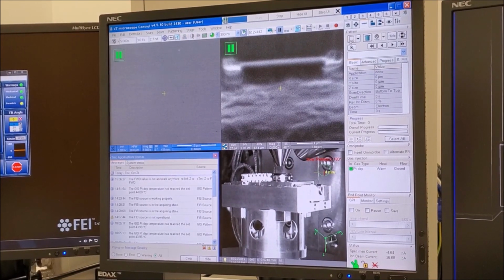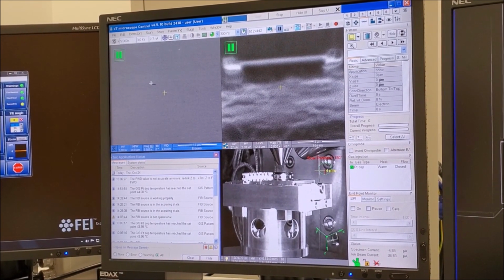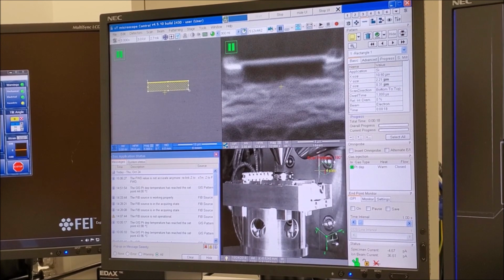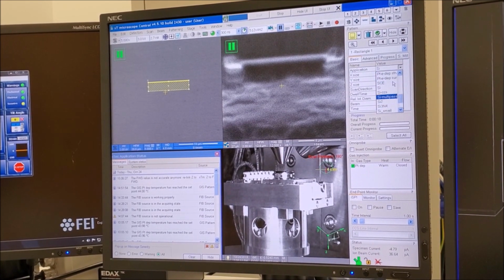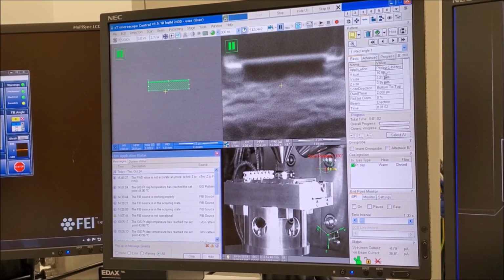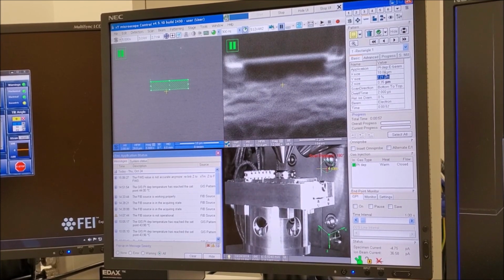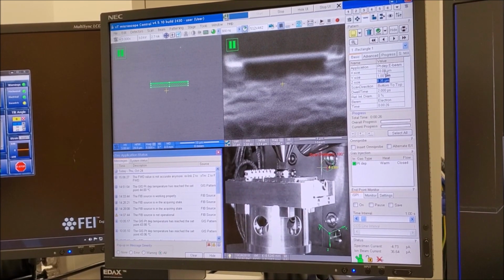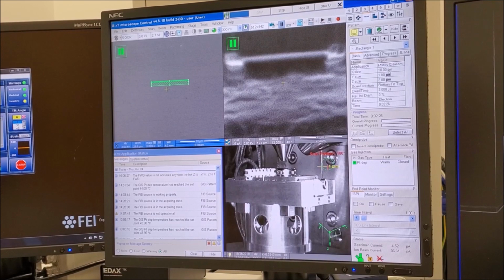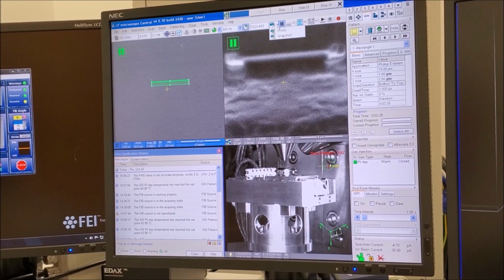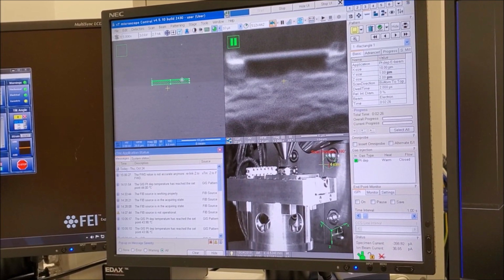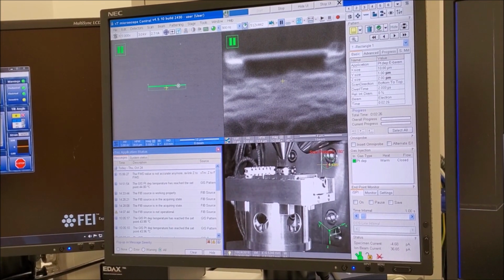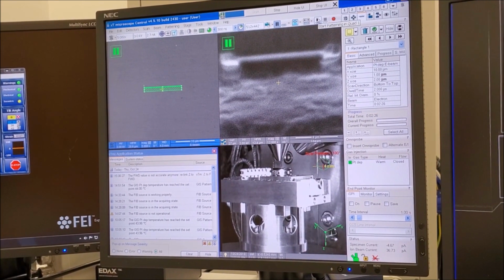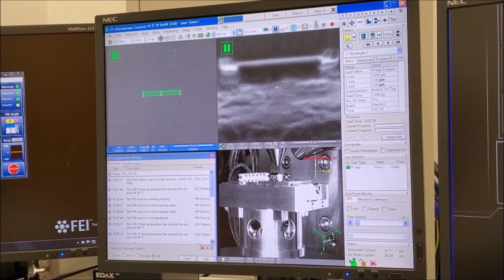In the patterning module, select the rectangle pattern and then click and drag on the electron beam image. In the Basic tab, change the application to PT Dep E-beam, and then you can also adjust the X, Y, and Z dimensions of the pattern as desired. Once the pattern parameters have been set, acquire another snapshot. Then click and drag on the pattern to position as necessary, and then select the play button to start the deposition.